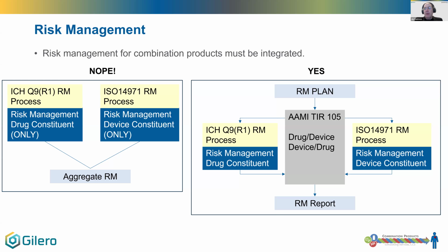And likewise, there could be a drug-device interaction that might not otherwise be seen if everything was looked at independently. For example, DMSO is an excipient, which is fine for storage, but during use, it interacts harshly with the plastic components of the device and causes a device failure. So it's very important to take these drug-device and device-drug interactions into account when conducting your risk management. And the way to do that is to have a risk management plan that integrates everything.